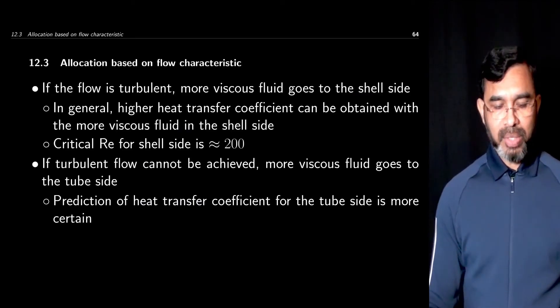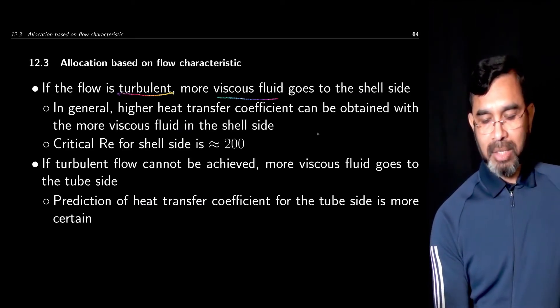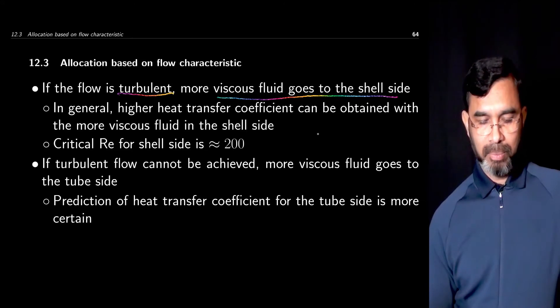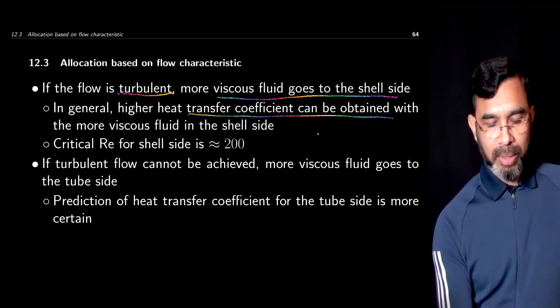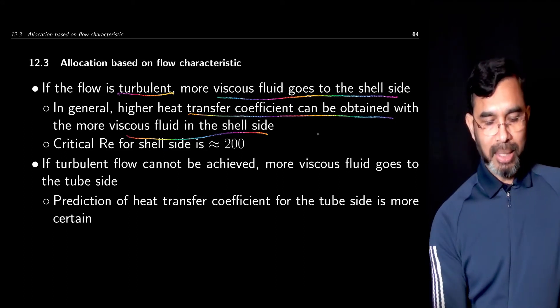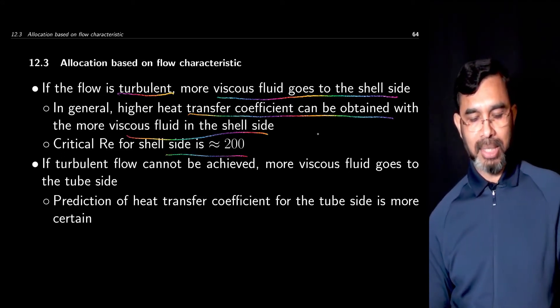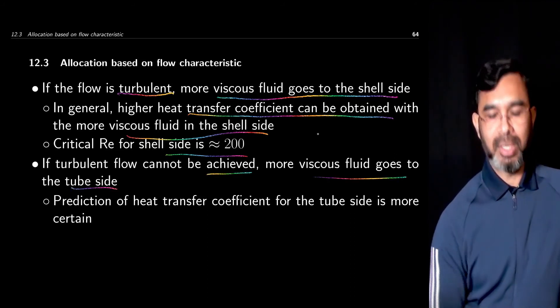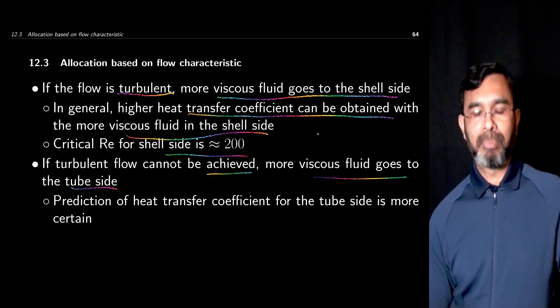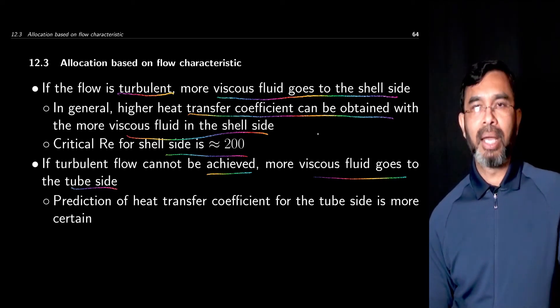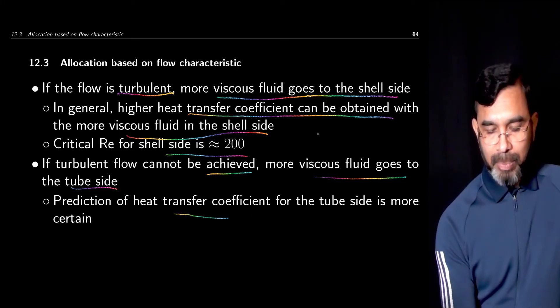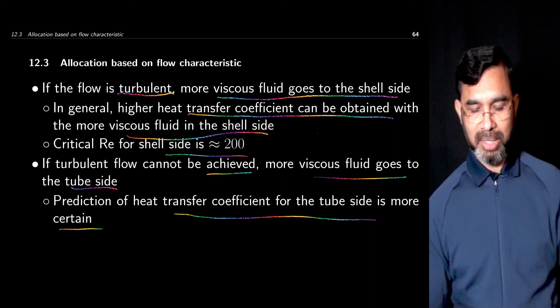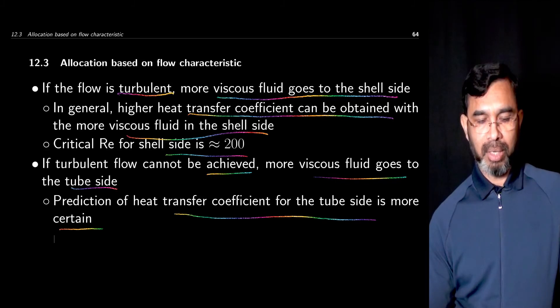Regarding flow characteristics, if the flow is turbulent, the more viscous fluid goes to the shell side because it is easier to create turbulence there. In general, a higher heat transfer coefficient can be obtained with the more viscous fluid on the shell side, and the critical Reynolds number for the shell side is around 200. However, if turbulent flow cannot be achieved, the more viscous fluid goes to the tube side, where higher velocity can be obtained, giving a high Reynolds number and eventually a high heat transfer coefficient. The prediction of the heat transfer coefficient for the tube side is also more certain compared to the complexity and errors in shell side heat transfer calculations.